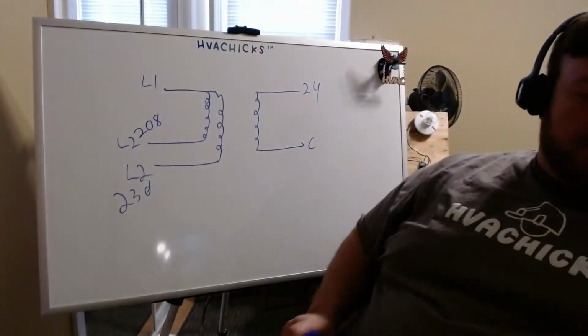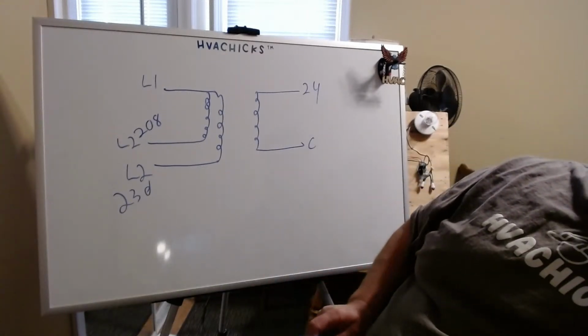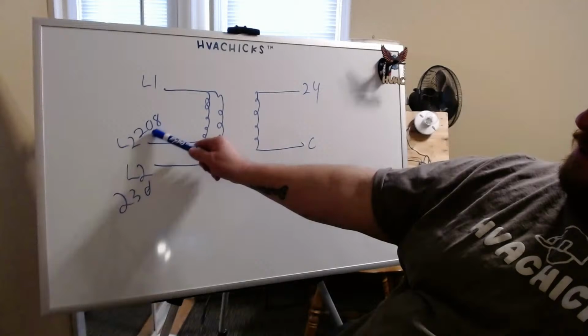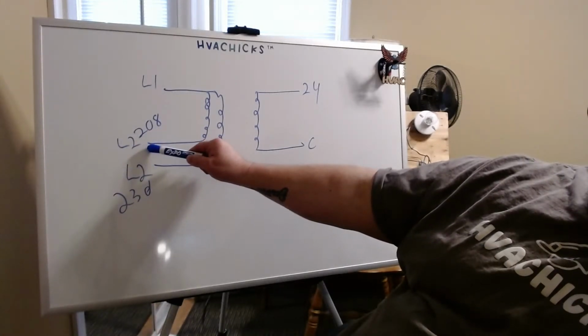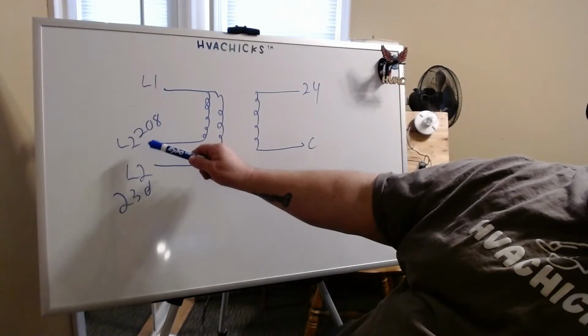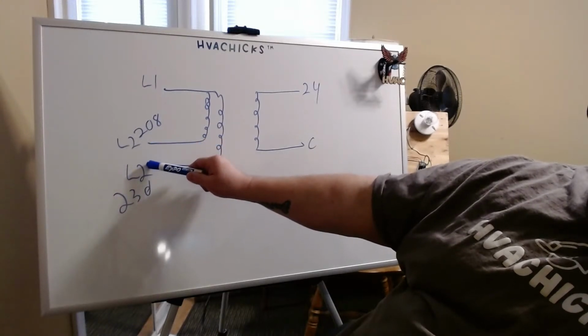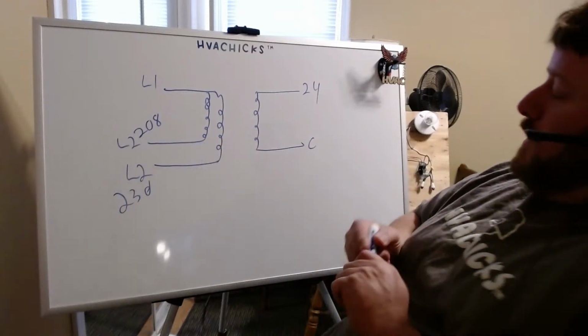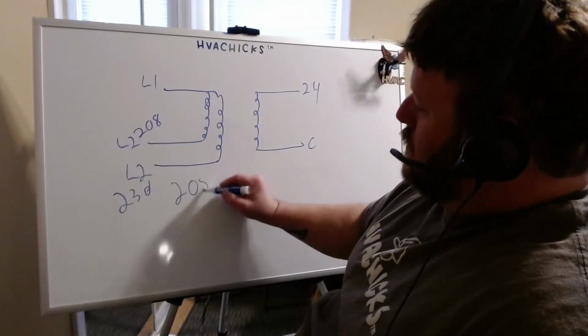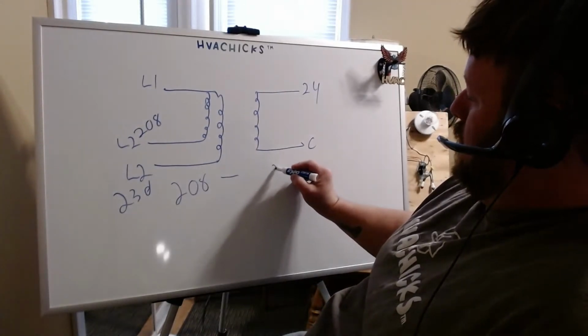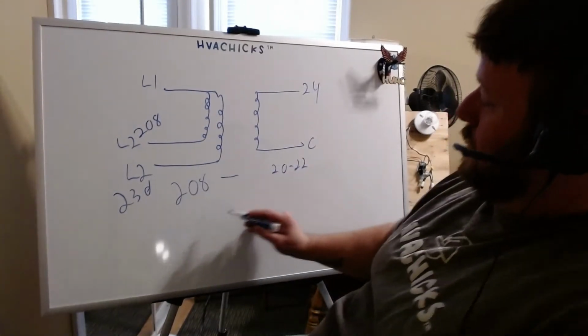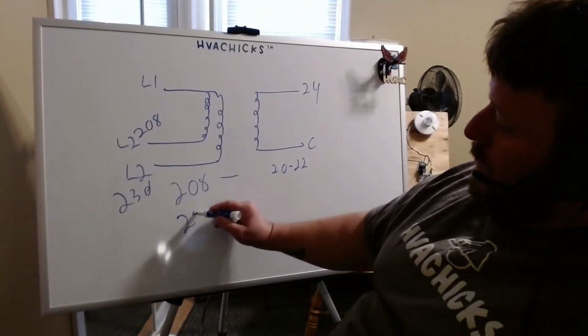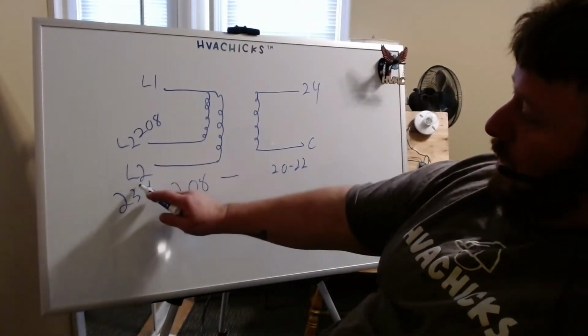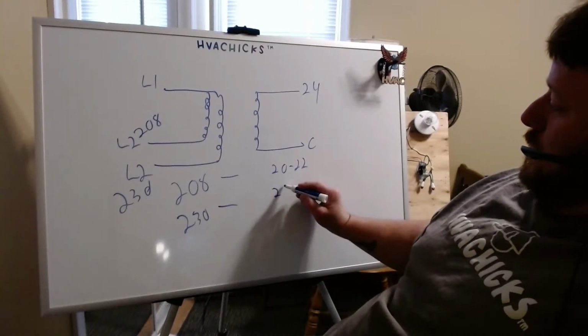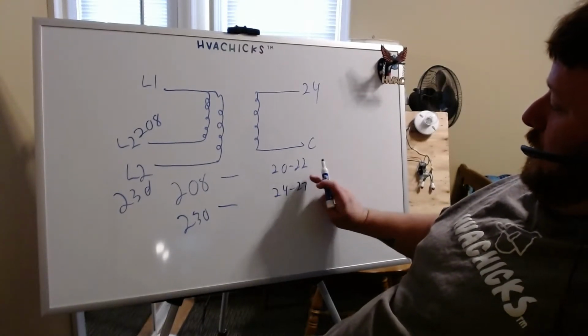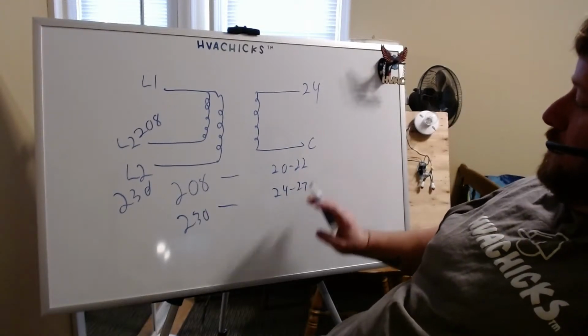So on transformers, if you're messing with a commercial unit, you will have a tap here that is right beside the 230 tap that says 208. If your line voltage coming in is 208, you need to move your wire from here to here. Reason being, on 208 volts to 24, you're going to get 20 to 22 volts, right? On 230, if we're still wired on the 230 tap, 24 to 27 volts roughly. Depends. Sometimes it's 26, but we'll just go with the 27.